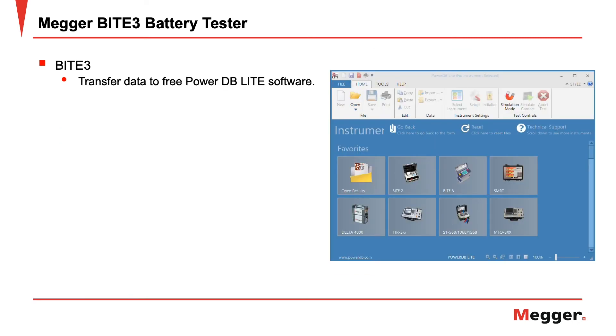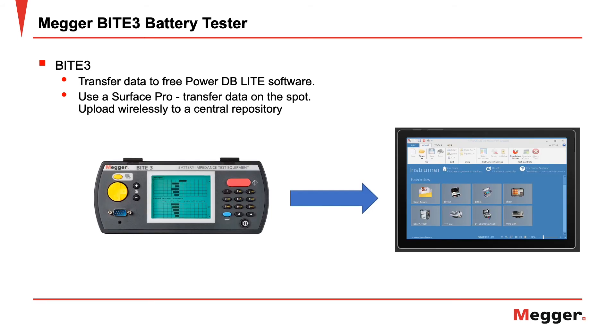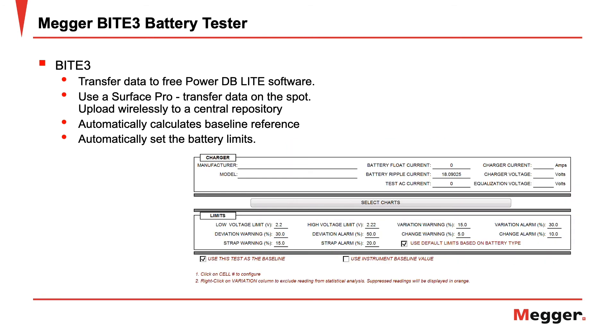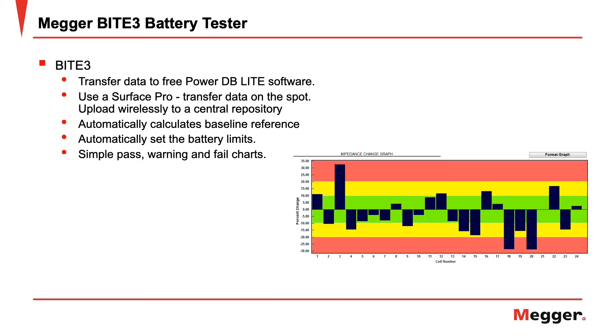You can transfer the data to the free PowerDB Lite software. You can use a Surface Pro to transfer the data on the spot, and the data can then be uploaded wirelessly to a central repository. The PowerDB Lite PC software automatically calculates the baseline reference value for each string, automatically sets the limits for the battery analysis, and each time you test the string the same baseline and limits are automatically used. Simply create a report and automatically see what passed and what failed.